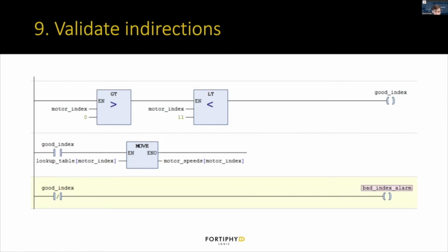And looking at an example in CODESYS, how you might do this. You just have some checking of ranges: if the motor index is greater than 0 and less than 11, then it is a good index. Then only if it is a good index, use that lookup table for that motor index to update the motor speed. Ladder logic is kind of more complicated in this example. Using structured text would make this a little bit easier to implement. But just the concept of before you use the variable from the array, do some checks on whether it is in a valid range or not. And if it ever is not in the valid range, you want to raise that alarm and log it.